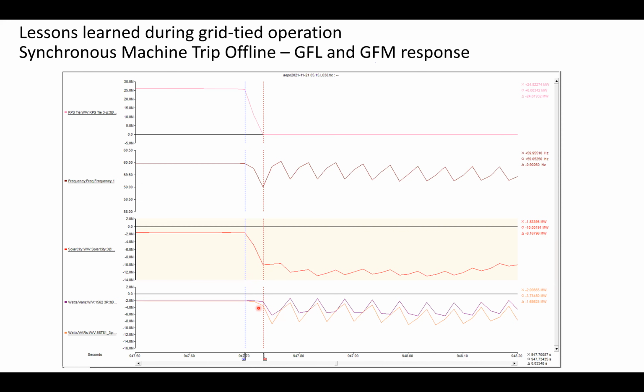And the difference here is not just the magnitude difference and how they seesaw back and forth, but it's also the delay that you're seeing in the grid following response. The difference between X and O here is about 2 cycles.